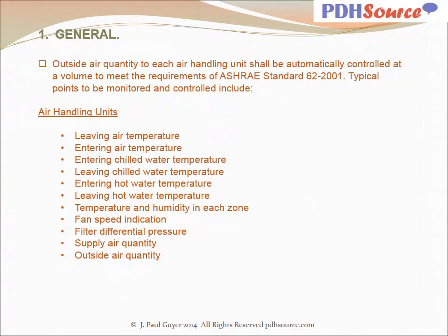Outside air quantity to each air handling unit shall be automatically controlled at a volume to meet the requirements of ASHRAE Standard 62. Typical points to be monitored and controlled include, for air handlers: leaving air temperature, entering chilled water temperature, leaving chilled water temperature, entering hot water temperature, leaving hot water temperature, temperature and humidity in each zone, fan speed indication, filter differential pressure, supply air quantity, and outside air quantity.